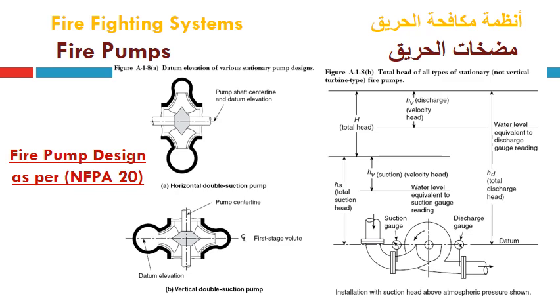This slide compares a horizontal double suction pump and a vertical double suction pump. On the left side, the upper one is a horizontal double suction pump where the shaft is located horizontally, and this is a plan. The impeller is affixed on the shaft, and this is the datum of the elevation of the center line of the pump. The suction flow is divided between both eyes of the impeller, and according to the rotational motion of the shaft the impeller will rotate and discharge the flow through this volute casing, from its smallest size until it reaches its maximum size at the discharge flange.